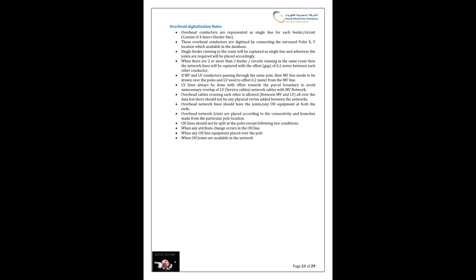Overhead network lines should have the joints or any OH equipment at both ends. Overhead network joints are placed according to the connectivity and branches made from the particular pole location. OH lines should not be split at the poles except under the following 2 conditions: when any attribute change occurs in the OH line, or when any OH line equipment is placed over the pole, when OH joints are available in the network.